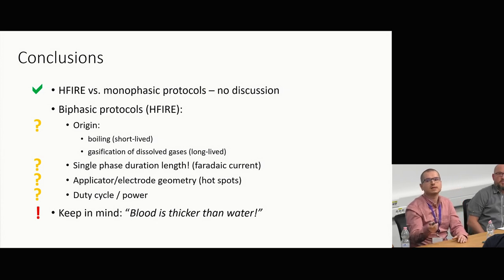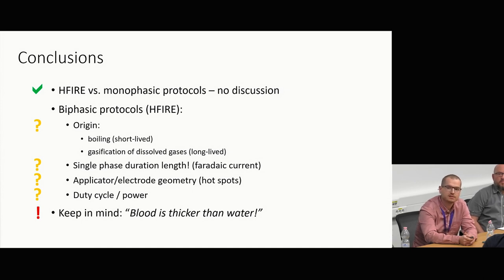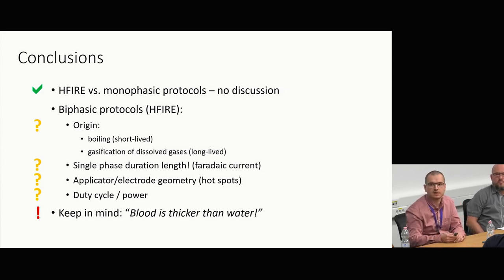In conclusion, there's practically no discussion H-fire versus monophasic, it's clear because of the actual chemistry. But in biphasic delivery we also have to be careful of some aspects. The protocol has to be designed such that it doesn't cause boiling of the medium or excessive heating that would lead to degasification. We also have to pay attention to the applicator and the geometry of the electrodes to avoid hot spots. Keep in mind that everything I was showing in my presentation was done in half normal or normal saline, and blood is not saline, so it's probably going to be more complicated.